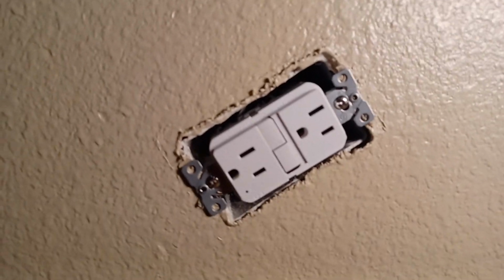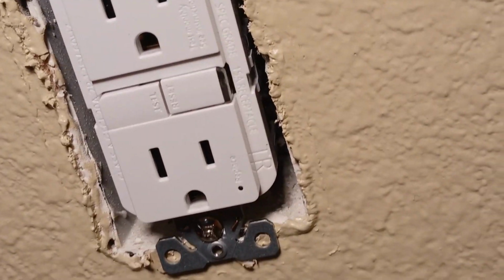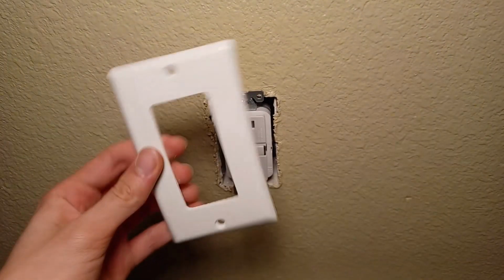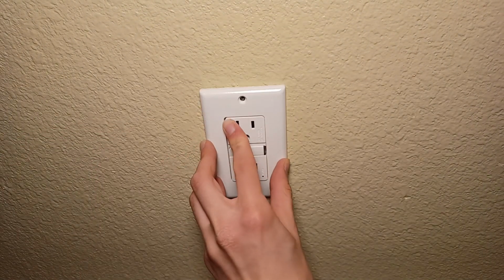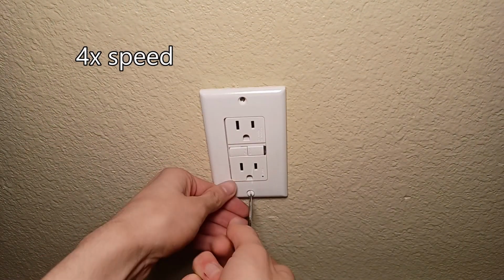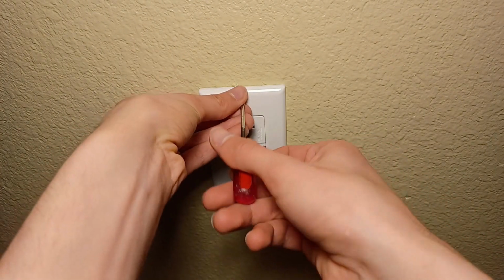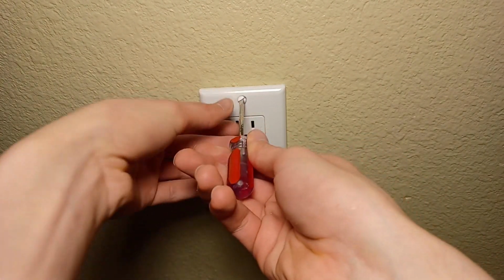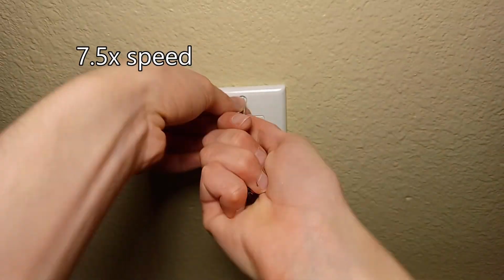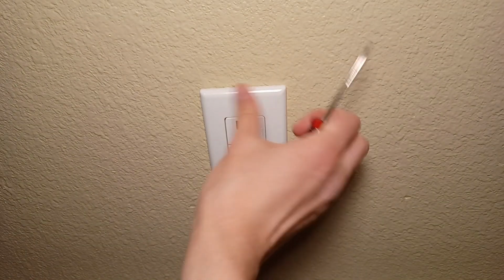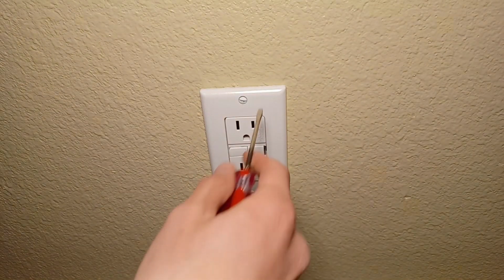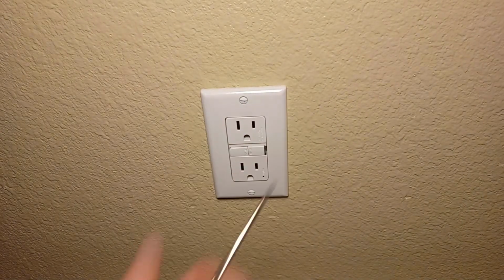Now we carefully look to make sure nothing is touching, shorting anything. Does not look to be. So we're good. Now the new rectangular cover plate can be installed. And the new plate includes these shorter screws. Make sure I don't put so much force I'll break this. Looks good. Now, time to turn on the breaker.